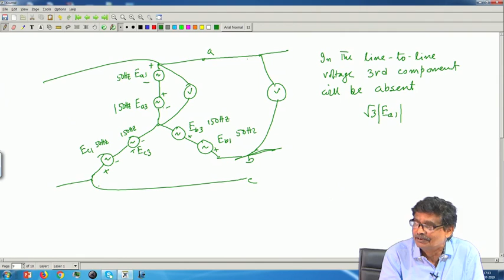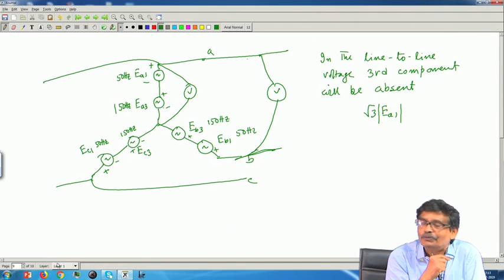But that notion is to be changed now, because similarly on the primary side there is a fundamental component voltage, and there is a third harmonic. Read this capital A 1, B 1, C 1 also the same thing. So between the lines only the fundamental will come. It is matching, so KVL is not disturbed so far as the supply is concerned. Only thing is that V L L by root 3 as phase voltage you will never get, because in the primary coils also the fundamental and third harmonic will appear.